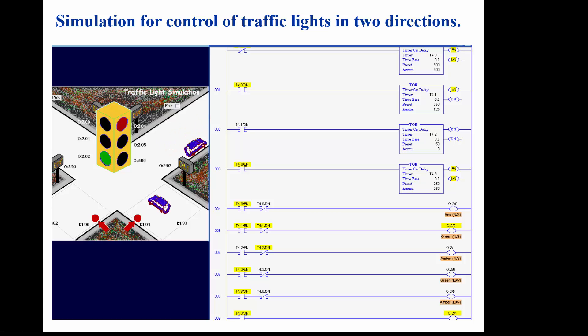At this step, T4:0 and T4:3 timers have completed timing. The done bit of T4:0 has started timer T4:1. The north-south green light is on and the east-west red light is on. Timer T4:1 has finished timing and started timer T4:2, which turns off the north-south green light and turns on the north-south amber light.